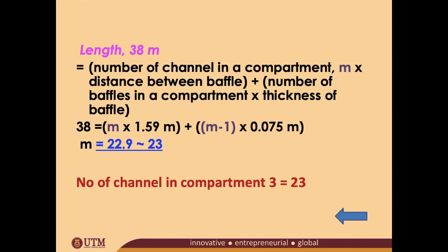Therefore, the number of channels in compartment 3 is 23. Because we have wider spacing, that means we're going to have less number of channels in compartment 3, just like the pictures that I showed you at the earlier part of this lecture. Okay, with that we have completed flocculation.